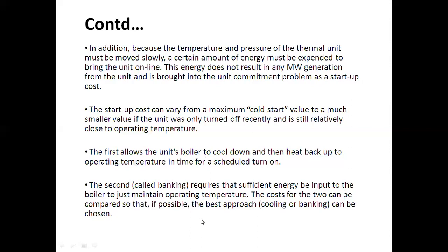The sufficient energy that is input to the boiler in order to maintain the operating temperature is known as banking. The cost of the two can be compared so that, if possible, the best approach, cooling or banking, can be easily chosen.